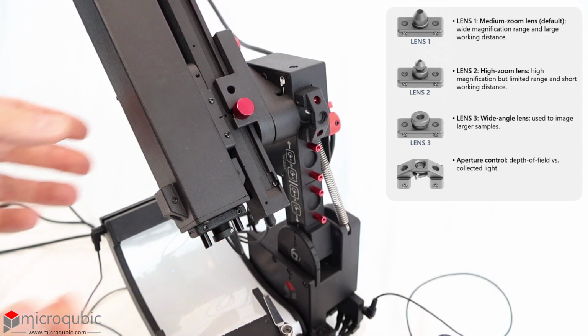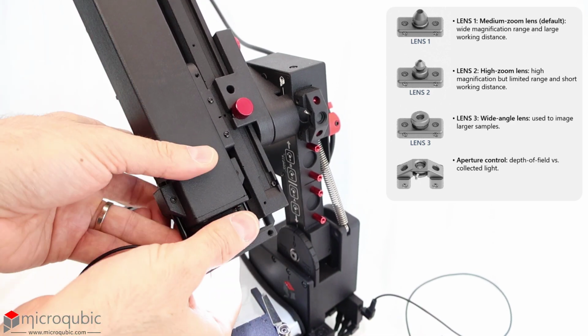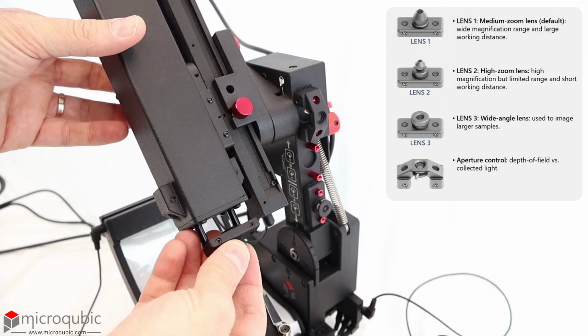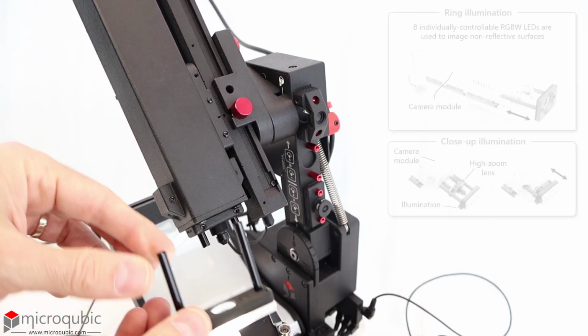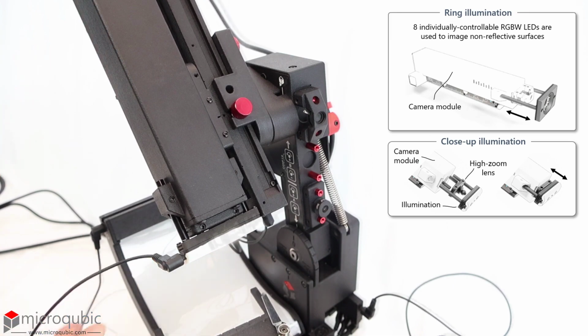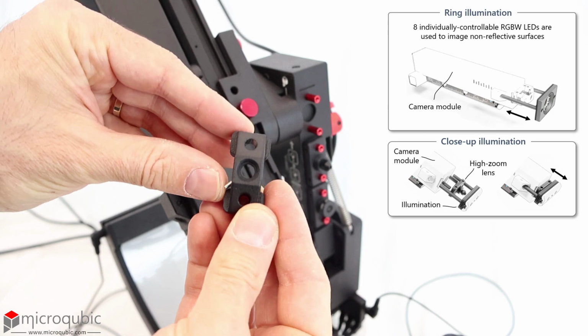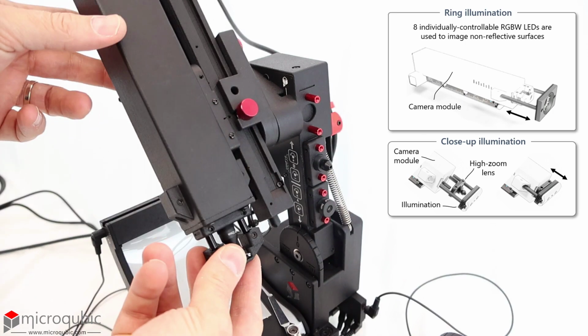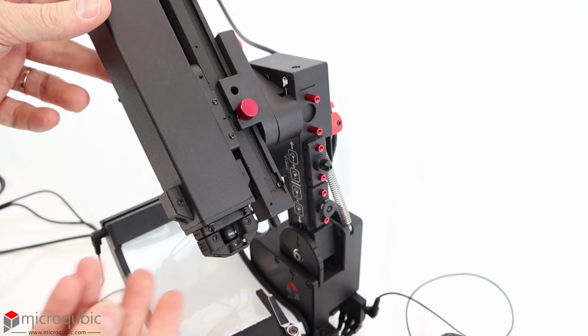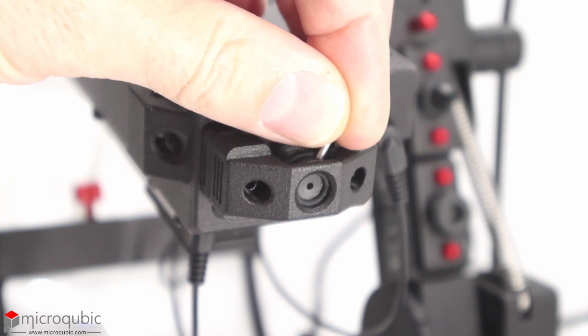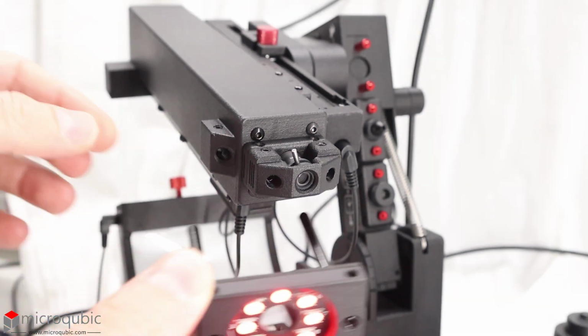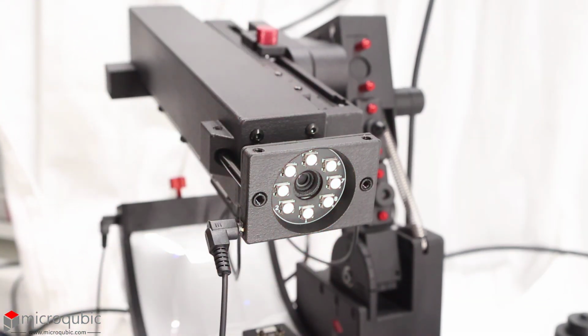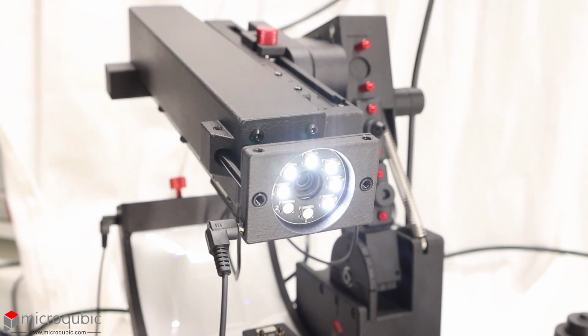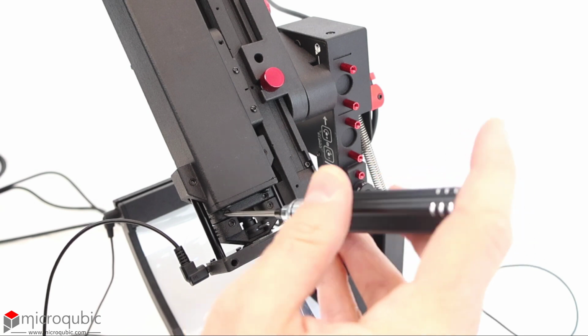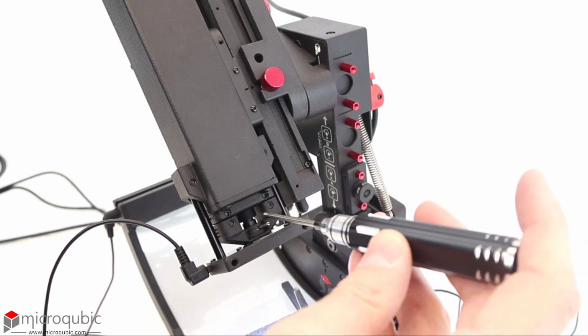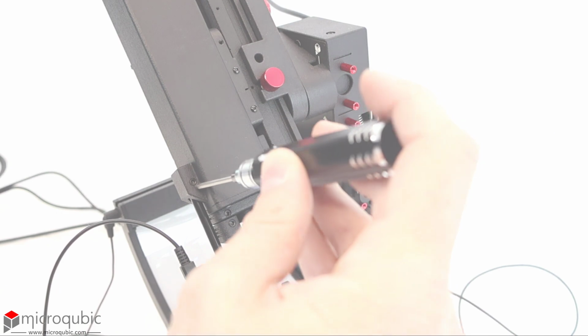These lenses have a spring-loaded insertion mechanism, allowing them to be interchanged easily. Illumination sources can be inserted in front of the lens. Other optical components, such as polarizers or filters, can optionally be added using custom-designed holders with the exact mechanism. A manually controlled iris diaphragm is also provided, and it can be placed in front of the lens to adjust the aperture. Please refer to the tutorial on operating instructions for the depth of field adjustments and focus stacking. The clamping of these insertion mechanisms can be adjusted using the provided screwdriver.